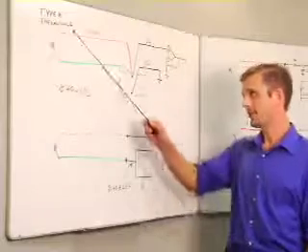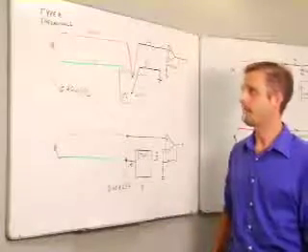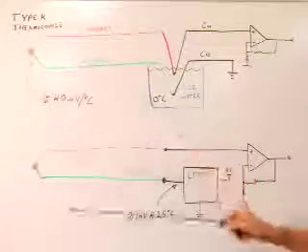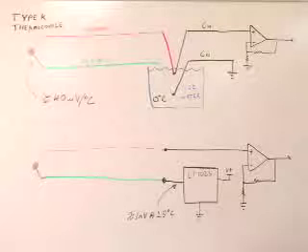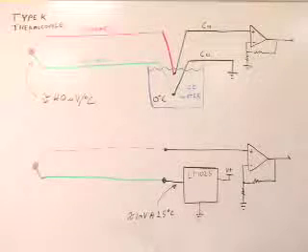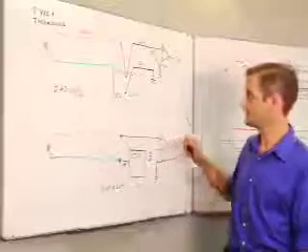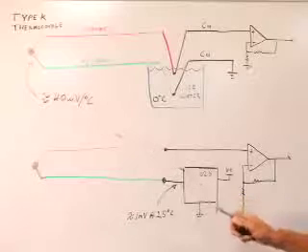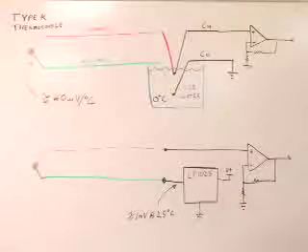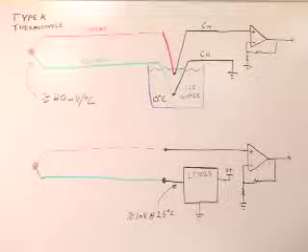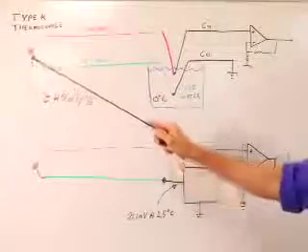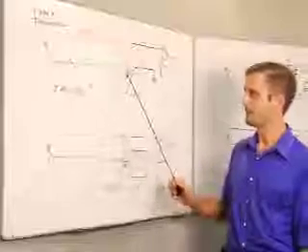So here's a schematic of how a type K thermocouple would typically be applied. The way a thermocouple works is it's two dissimilar metals in which a temperature gradient along the wires produces a voltage gradient. And the two different materials have different gradients that result in a net voltage difference at the cold end of the thermocouple. So a type K thermocouple has an output of approximately 40 microvolts per degree C. And that's the difference between the hot end of the thermocouple and the cold end.